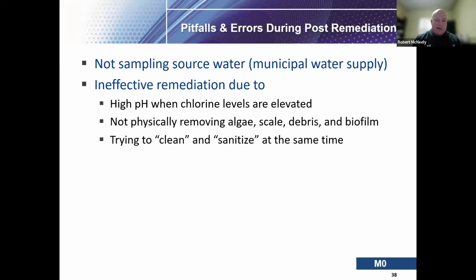Ineffective remediation can happen when pH is too high, especially on some systems - around 9.5 - where most oxidants won't work or are completely ineffective, not in the right form to disinfect. Not physically removing algae, scale, and biofilm is also a problem, as is trying to clean and sanitize at the same time. That's a big no-no - you need to clean first, then sanitize separately.